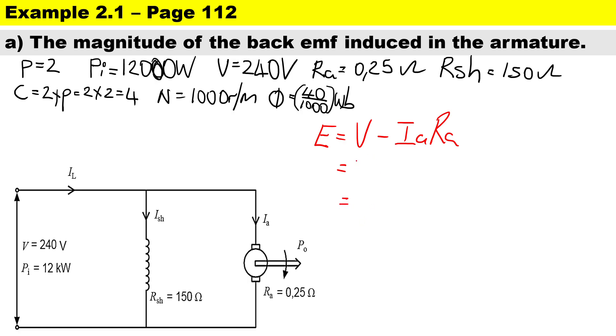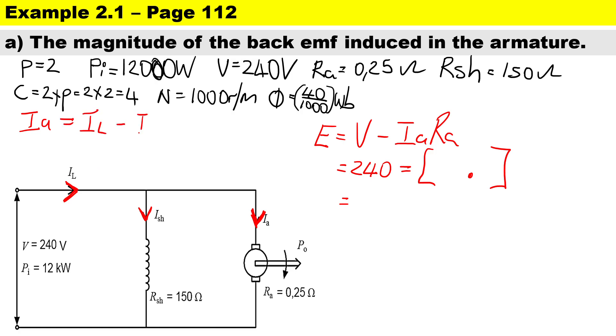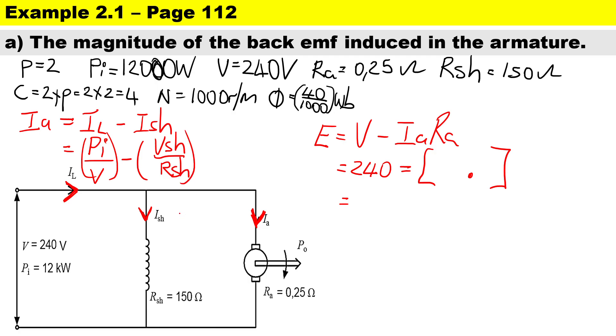We have the terminal voltage of 240 volts and the armature resistance, but we need to calculate the armature current. For a motor, I_a = I_L − I_shunt. Most of the supply current is drawn by the armature and a small amount flows through the shunt resistor. The line current is calculated as input power divided by voltage, and the shunt current is V_shunt divided by R_shunt. Since the shunt winding is connected in parallel, its voltage equals the terminal voltage.